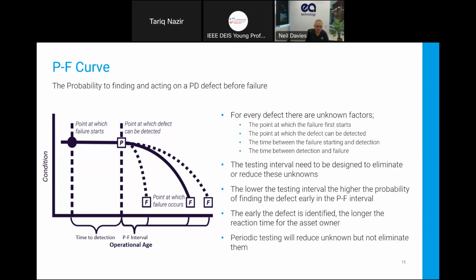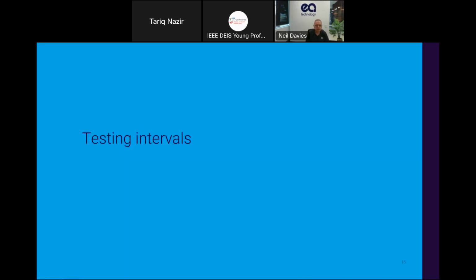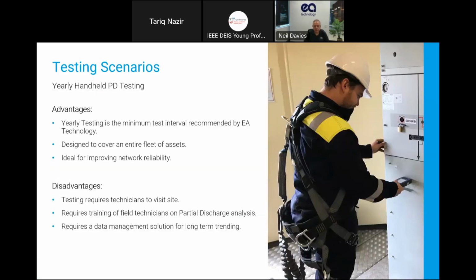So all these make the question of how often we should test and when will it fail difficult, because this P2F interval can be so very variable. So let's talk about testing intervals and different regimes that people use and adopt frequently. Now, our starting point as an organization really is, if you're starting testing switchgear, an annual PD test is at least a good starting point. Sort of what we would consider the minimum test interval.